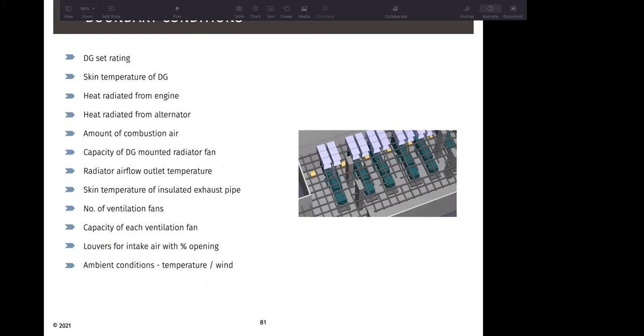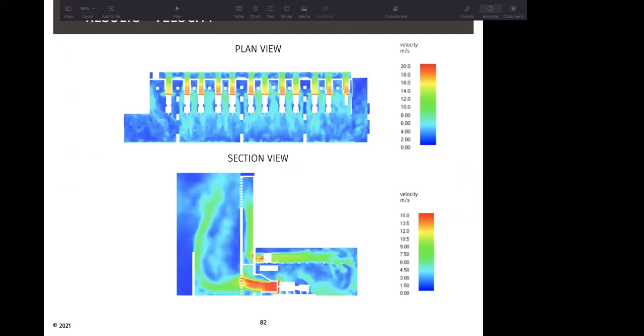Now for the same analysis, the boundary conditions to be considered are the skin temperature of the DG set, the heat radiated from the engine, heat radiated from the alternator, the amount of combustion air, the capacity of each DG-mounted radiator fan, the radiator airflow outlet temperature, the skin temperature of insulated exhaust pipes, number of ventilation fans, capacity of each ventilation fan, the louver for intake air with percentage opening, and the ambient conditions like the dry bulb temperature and the wind condition. And what we can see in such an analysis is whether the air being pushed from the DG radiator side is being pulled back into the intake side.